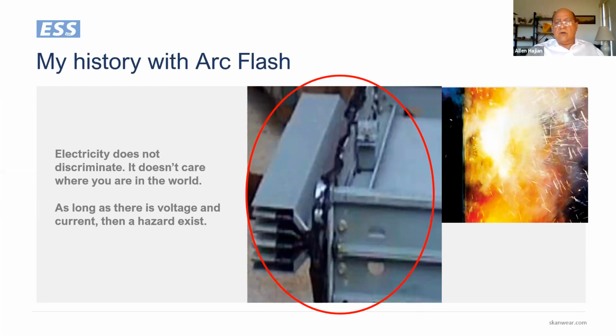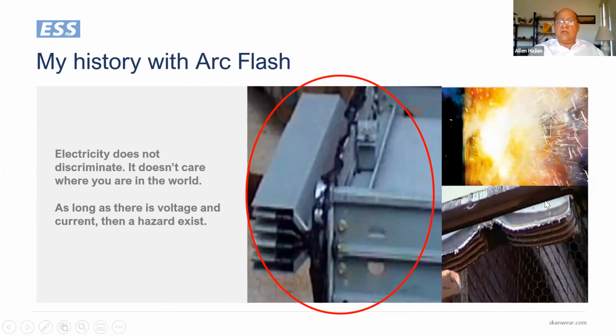The area I have in the circle, you can see on the bottom right corner, is completely evaporated. Imagine the energy that it takes to evaporate 3 kilograms of copper and steel. That is completely gone. That kind of energy is available in an electrical system. This was a low voltage system. This was a 480 volt bus duct connected to a 2500 kVA transformer. As you know, a 2500 kVA transformer is used in industry and in shopping malls; it's a very common transformer for electrical distribution.